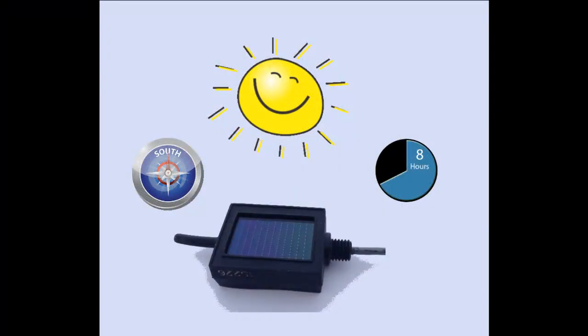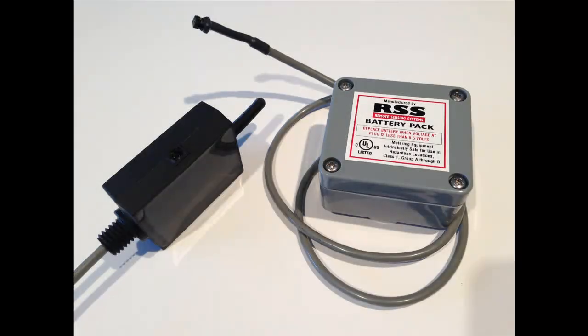Once the transmitter receives enough solar energy, approximately 6 to 8 hours of sunlight, it will begin to send messages every 8 to 10 minutes. If there is not sufficient time to charge the wireless transmitter for the recommended 6 to 8 hours, an optional battery pack can be purchased that will allow the technician to get immediate results from the transmitter for the initial setup procedure.